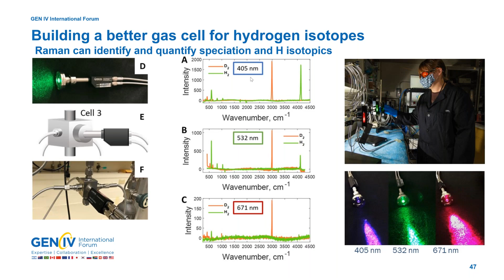In this case, 405 nanometer excitation gives a lot better sensitivity for deuterium and hydrogen measurement. This is the deuterium band here at about 3,000 wave numbers, hydrogen band around 4,000 wave numbers. Very large separation between those two signals. Very nice, easy way to measure this using the Raman technique. As you go down to 532 or 671 nanometer excitation, you can tell that the scale is less sensitive as we go to longer wavelength excitation. And you can also see the ratio between the deuterium and hydrogen isotopes is much different as well. So in this case, we use the 405 nanometer excitation.